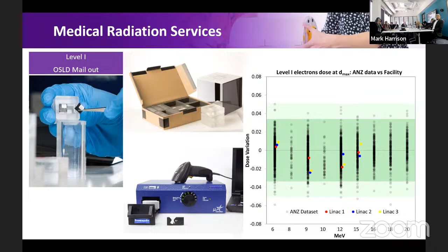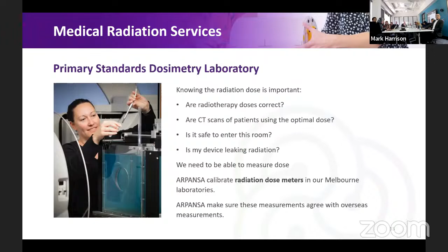So again, this all sits adjacent to and sort of on top of a primary standards dosimetry laboratory. So ARPANSA has primary standards. We have 3 of them. We have one in the megavoltage space, one in the hard kV, and one in the softer kV. We maintain all of them under authority from the National Measurement Institute, under which we not only maintain these instruments to an appropriate level of quality, but also disseminate them, which means we calibrate chambers sent to us by facilities around the country and a number of internationals to ensure that their fundamental radiation equipment is giving the appropriate reading for the appropriate dose.